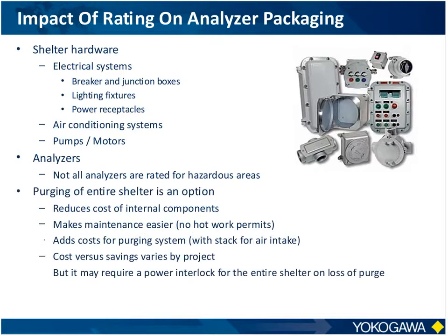One thing you might do is what's called purging the entire shelter, where you bring in fresh, known-safe air in large quantities to constantly flush out or sweep the area inside the shelter. This prevents the accumulation of hazardous gases, and it's handy because it reduces the requirements for your electrical equipment, making it a lot cheaper.